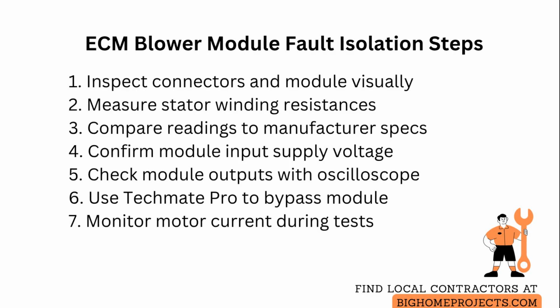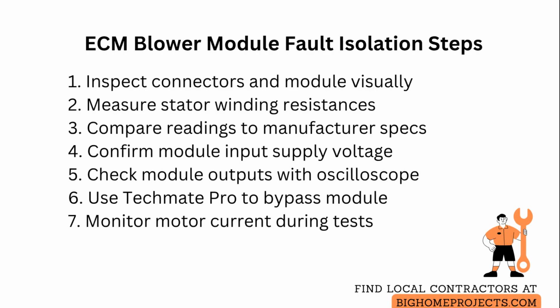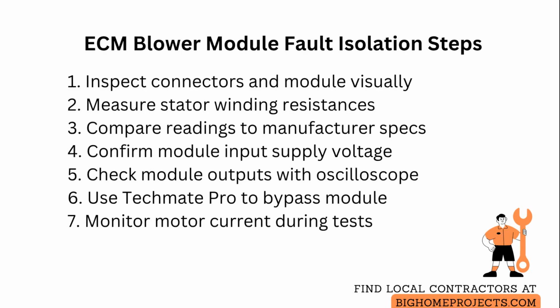Compare readings to the manufacturer specified values because significantly higher or open readings point to motor winding failure, while near specification values suggest the module could be at fault.